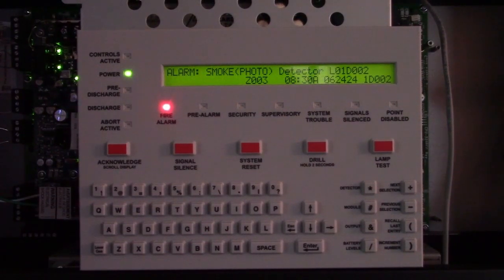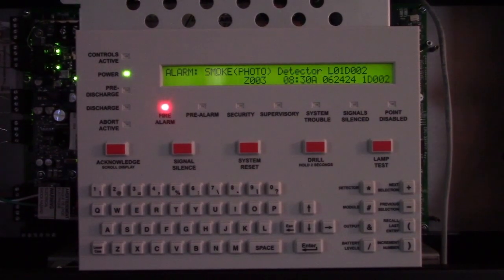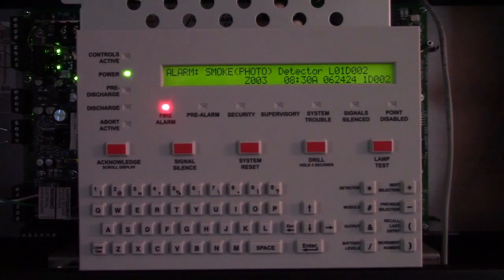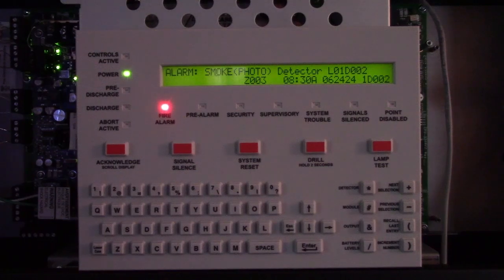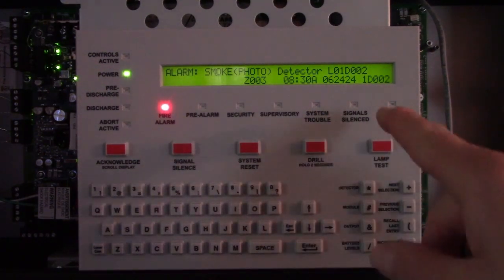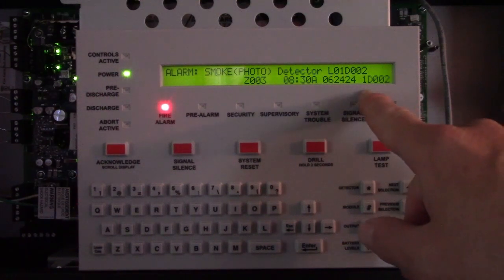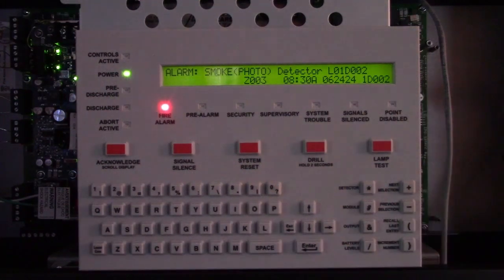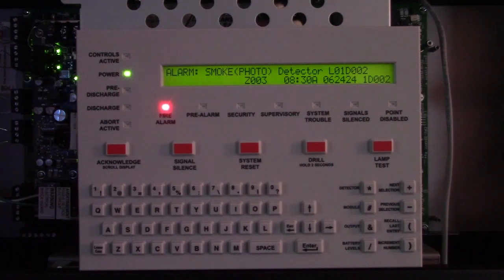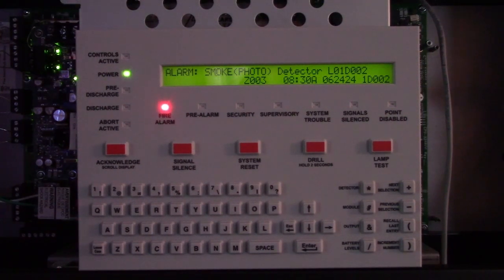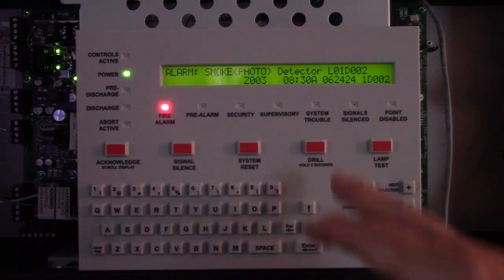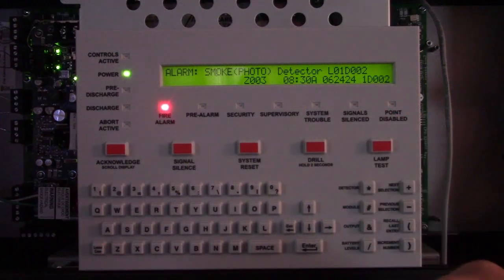This video is to disable a point on a Notifier 320 system. In this example, there's a smoke detector currently in alarm. This address is loop 1, detector 002. Perhaps it's in a tall atrium and you're going to need a lift to service it, so for the time being we'll disable the detector until the lift can be obtained.